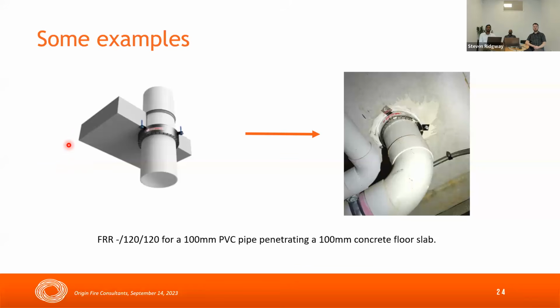And we choose which fire stop system we need to use based on what we're going to install on site. So let's say on this job, there's a PVC pipe penetrating the floor slab. We go to this manufacturer and choose this product. There are various other products you can install here, like a mineral wool batt and an intumescent wrap, if it is tested to this configuration. Yes, so we have a lot of options. We look at different manufacturers, their data sheets, their installation instructions, how much information they provide, and how easy it is to install. Based on that, we choose the product, and then we put it in our spec and give it to the client.